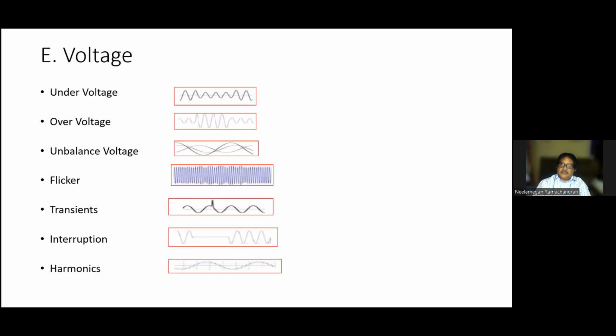Over voltage, the compensation will trip and there will be some problem. So what do we have to do? We can't change the tap of the transformer. We can't change the tap of the transformer every Sunday and come back to it on Monday. It's not possible. So we have to coordinate with the EB people and say the medium should be 430, it should not go more than 430, and it should be in the 410 range. So in dedicated feeders and factories very near to the substation, we get this problem. And under voltage, most of you would have experienced in the tail end areas.